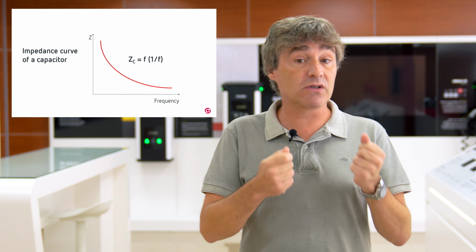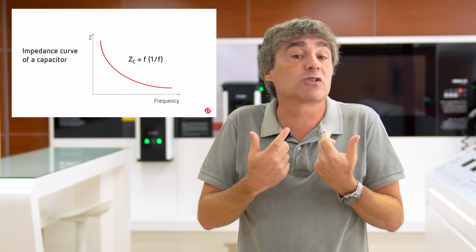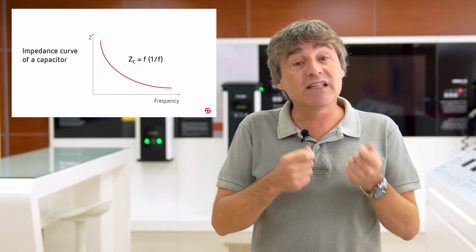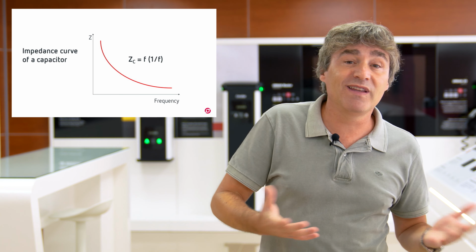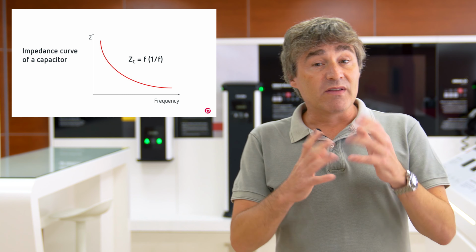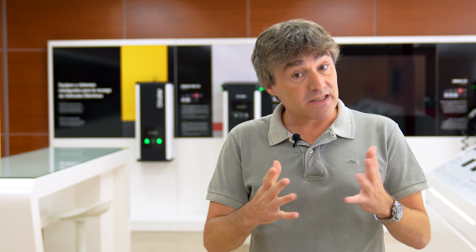Therefore, if a capacitor is connected to a power system that has some level of harmonic distortion, it is always going to be overloaded to a certain degree. However, this will not usually be the gravest problem that could arise, since there is the parallel resonance phenomenon, which basically involves the amplification of the current harmonics already existing in the network before the capacitors are connected to it. That is, the existing harmonic rates in current and voltage rise when the capacitor bank is put into operation.